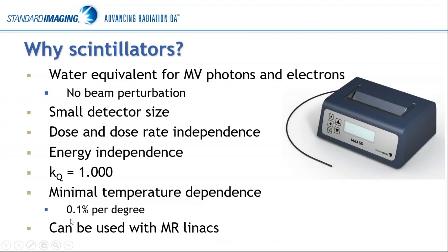So, without further ado, why scintillators? I get that question a lot when we first talk about them. Why would you use a scintillator? The main motivating factor is that these are water equivalent for MV photons and for electrons. The real advantage of this, particularly for small field dosimetry, is that you're not perturbing your beam right at the point of measurement. And so you don't have a whole list of field size or energy dependent correction factors to apply to your measurement in order to get back to that dose to water.